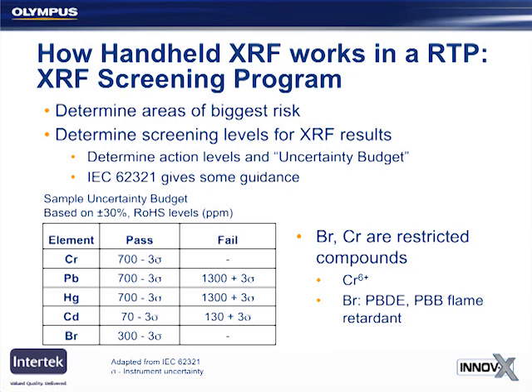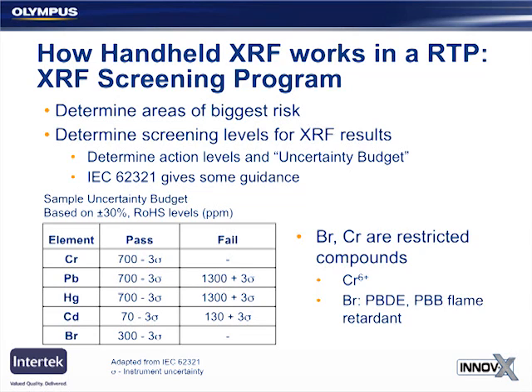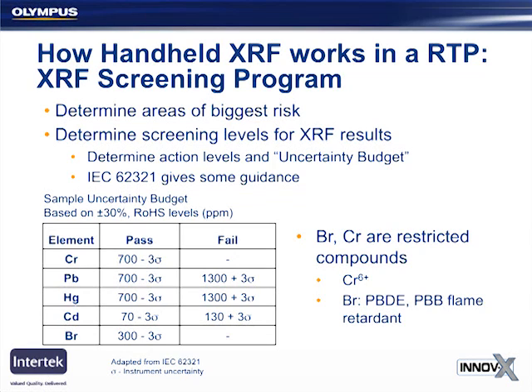So the IEC also recommends having a buffer zone around your screening levels, and that's known as the uncertainty budget. That's what the IEC document calls it, the uncertainty budget. The uncertainty budget is the sum total of all of the limitations of your technique, limits on sample preparation, limits based on what calibration you're using, and may include possible user error. And if your result falls within that area of uncertainty, you may need to do additional testing in order to ensure your product is compliant or be sure your product is not compliant.